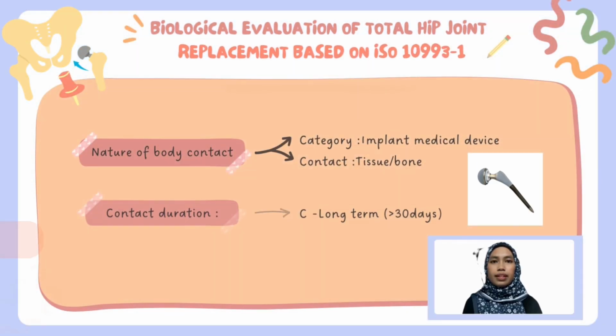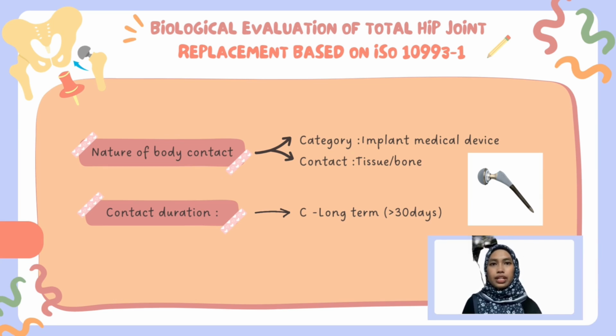Thank you. Next, I will continue with the third question. Biological evaluation of total hip joint replacement based on ISO 10993. From the table in ISO 10993, medical device categorization consists of nature of body contact and contact duration. Hip joint replacement is in the category of implant medical device and is in contact with tissue or bone. Medical implants are devices or tissues placed inside or on the surface of the body. The contact duration of the device is long-term, which is more than 30 days.